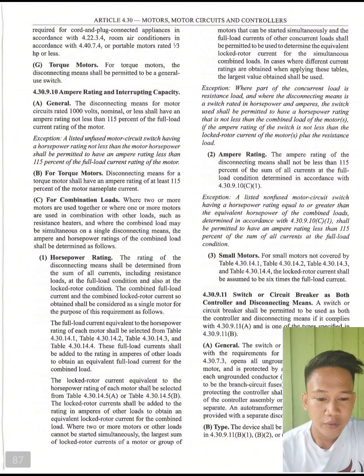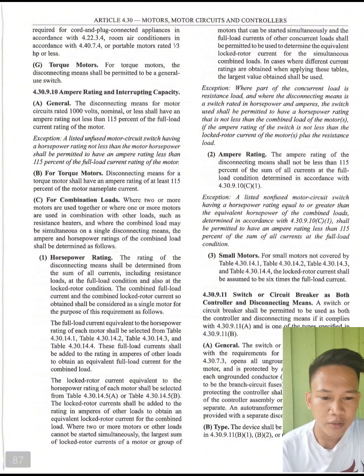The full load current equivalent to the horsepower rating of each motor shall be selected from Table 4.30.14.1, Table 4.30.14.2, Table 4.30.14.3, and Table 4.30.14.4. This full load current shall be added to the rating in amperes of other loads to obtain an equivalent full load current for the combined load.